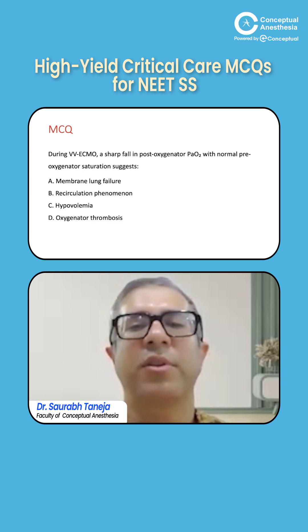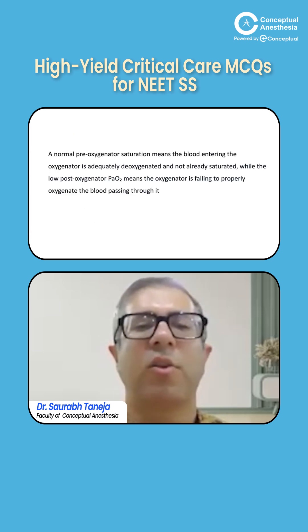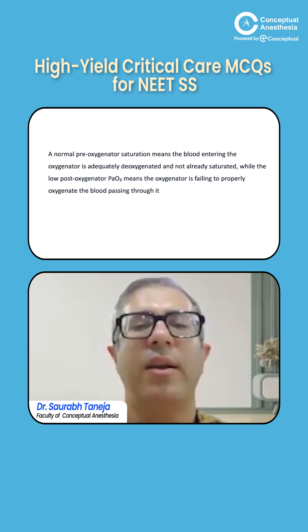But the post-oxygenator PO2 should be very high. If there is a sharp fall, that means there is some issue with the oxygenator, which is also called the membrane lung. Normal pre-oxygenator saturation means the blood entering the oxygenator is adequately deoxygenated and not already saturated. While a low post-oxygenator PO2 means the oxygenator is failing.